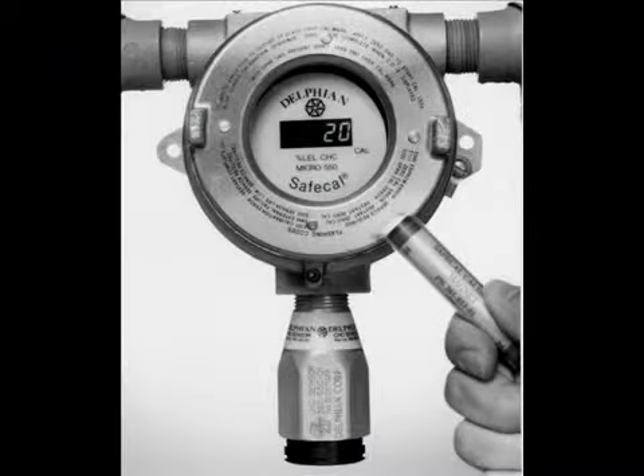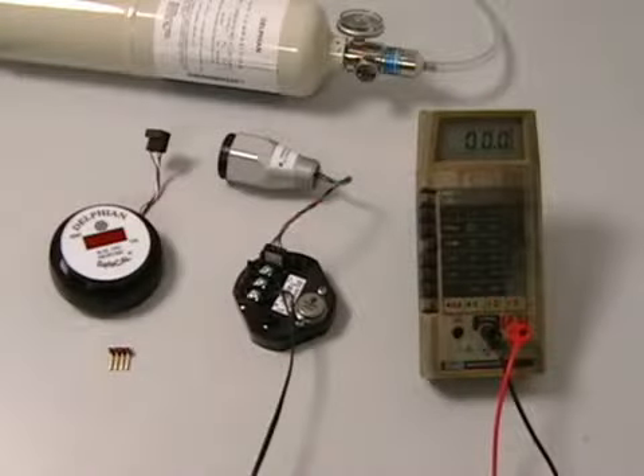There are several ways to troubleshoot a 550 catalytic bead system. You can test in the field, or you can swap components in the field and bring into house the parts to be tested under better conditions. An alternate instructional tool to this video is located in the 550 Operation Manual, Chapter 5, called Troubleshooting and Repair.